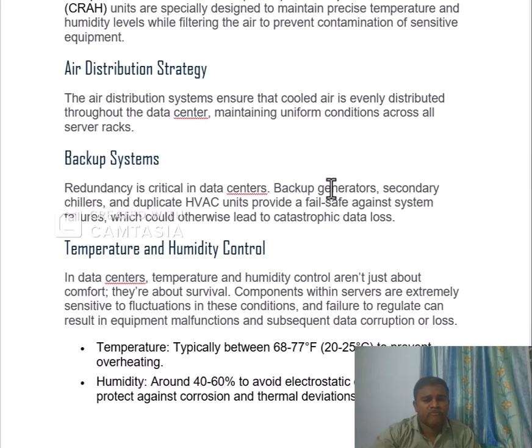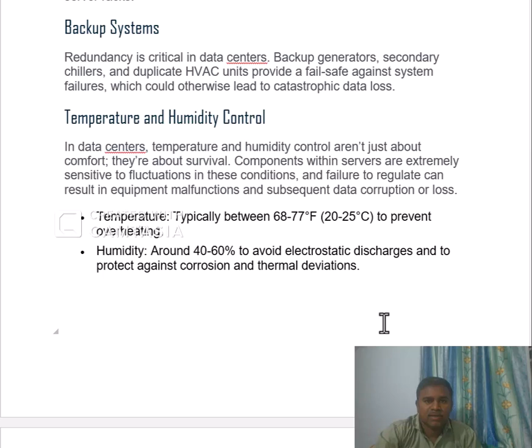So coming to temperature and humidity controls, the temperature should be between 20 to 25 degrees Celsius to prevent overheating, and the humidity can be around 40 to 60%, with 50% being usable to avoid electrostatic discharge. So guys, I am telling you, you have to remember these two points, very important, because somebody may ask what the temperature control inside a data center is, and you need to remember these things. So, the most common challenges that data centers encounter.